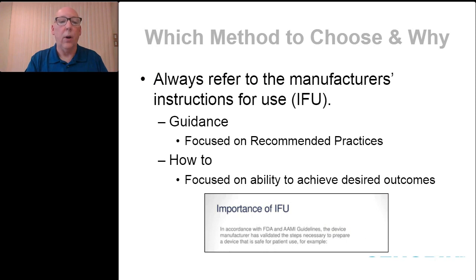Now, which method to choose and why? Well, we always want to refer to the manufacturer's instructions for use, IFUs. That starts with everything, right? They'll give you guidance in terms of providing guides focused on recommended practices and how to dry a device, focused again on the ability to achieve desired outcomes. And again, just with other processes in sterile processing departments, you always want to check with the device manufacturer regarding those instructions. If mechanical drying is used and is listed, the IFU can direct you regarding temperature, amount of time necessary, etc. So always, just like with any other process in sterile processing, check with the IFU of the manufacturer, and they'll give you guidance and recommendations relative to how to dry a specific device, as far as how long and temperature ranges as well.